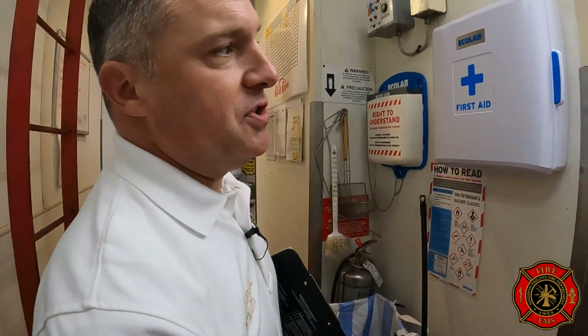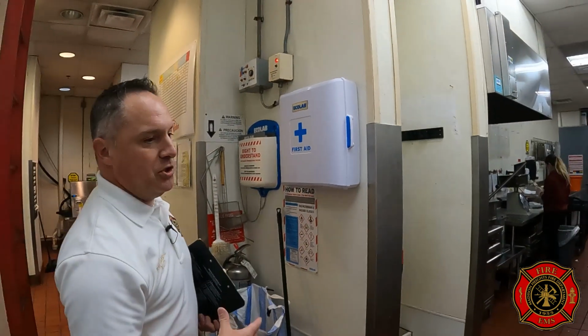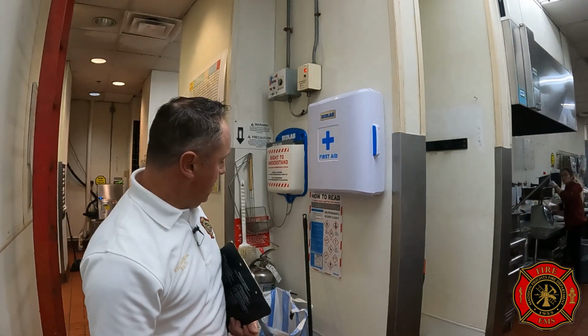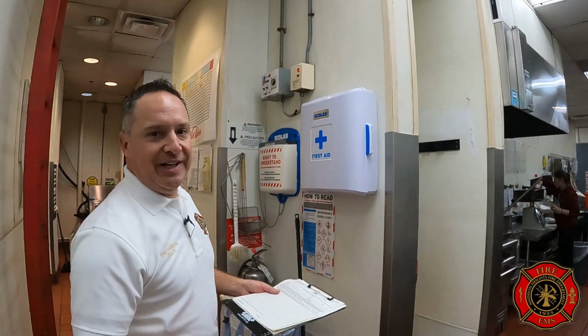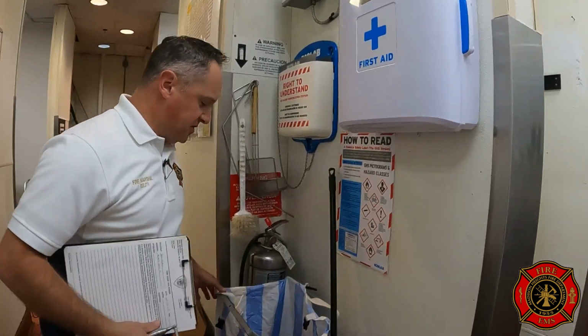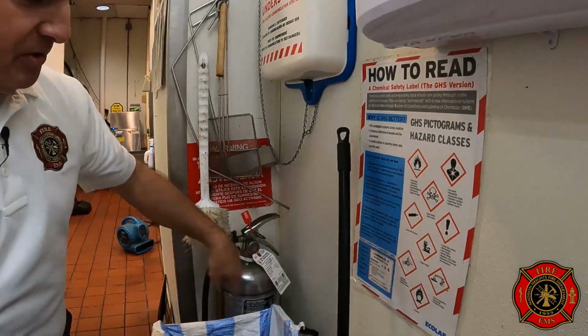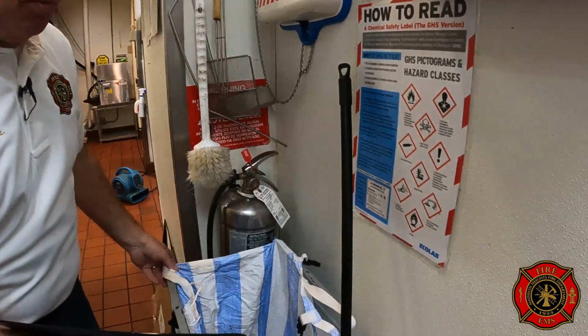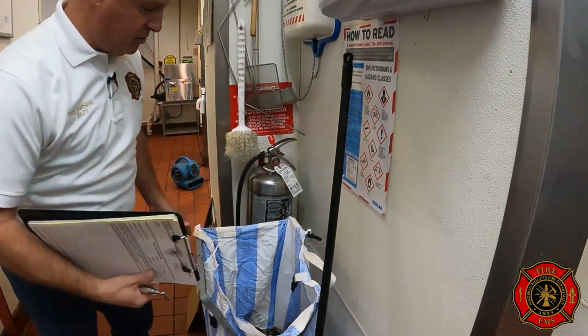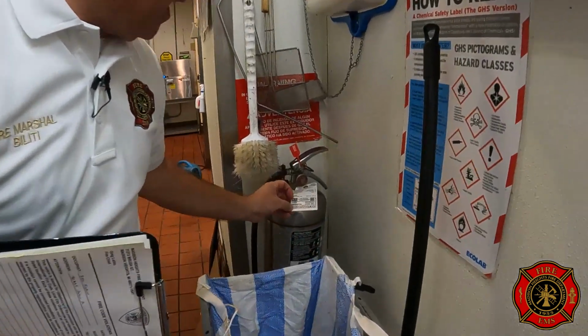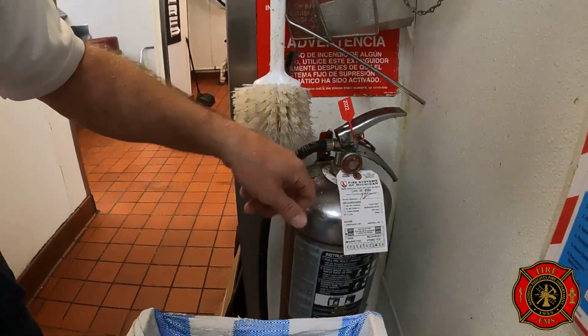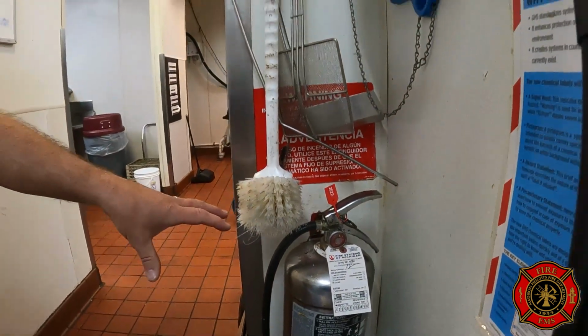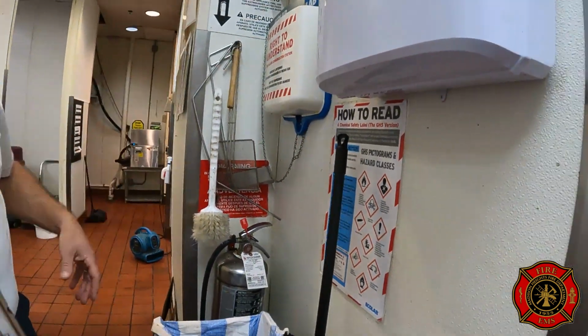When you have a hood suppression system with a cooking system, you also have to have a certain type of fire extinguisher, called a K-class extinguisher - the silver ones. We want to make sure there's free access to this, so we're going to ask them to move this laundry basket. Again, I'll check the date it was inspected and the pressure inside, and it's good to go. It needs to be within 30 feet of their hood suppression system.